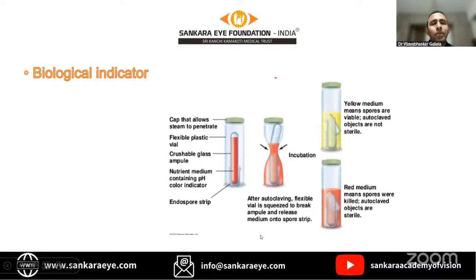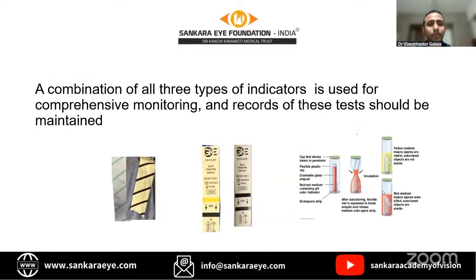Of course, ideally we should use it every day, but if not every day, make a policy that you use this biological indicator at least once weekly. There are different types for the autoclave, and for ETO also we should use this one. But ideally, not only one type, whether physical, chemical, or biological; the combination of all three types of indicators should be used for comprehensive monitoring.